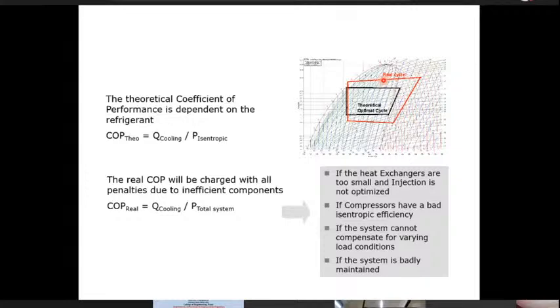So these factors, then the compressor will never have isentropic compression. So there will be an isentropic efficiency. How close is it to the isentropic compression process? This is because of the lubrication needs. This is because of pressure drops in the valves and some of the heat addition that is happening in the compression process because of the pistons rubbing against the cylinder walls.